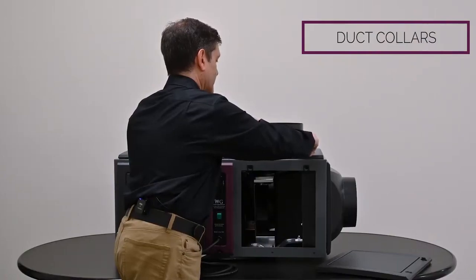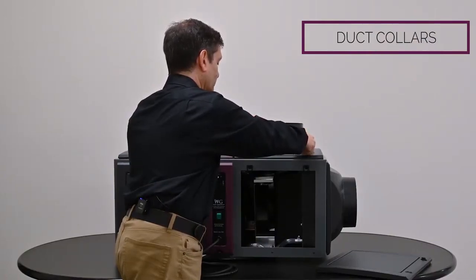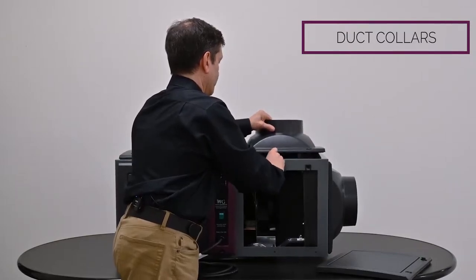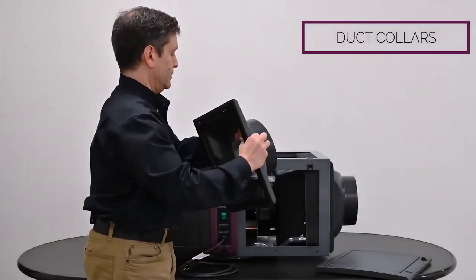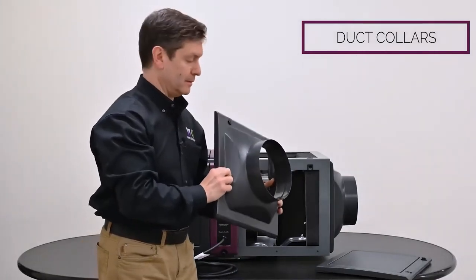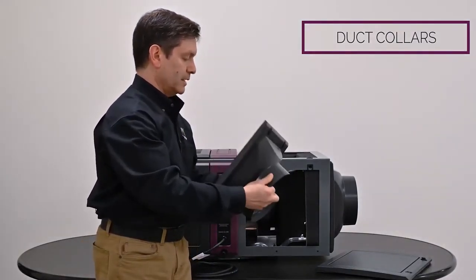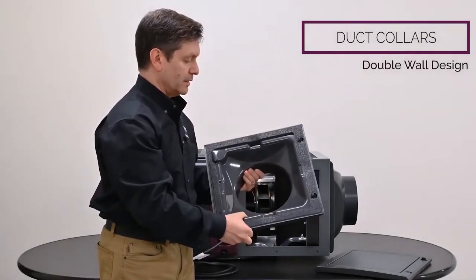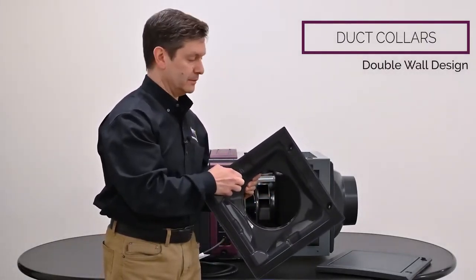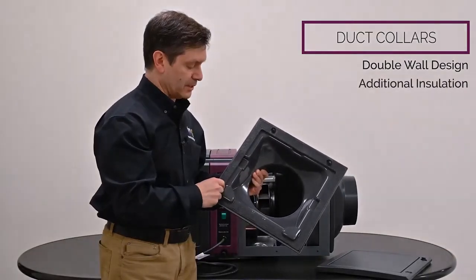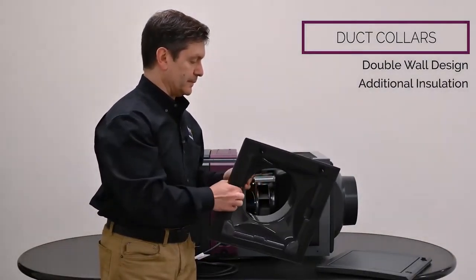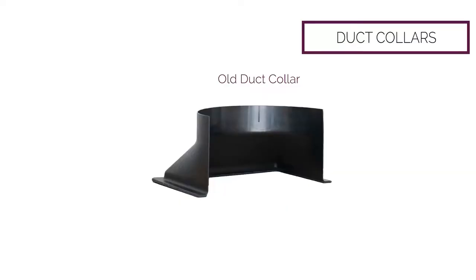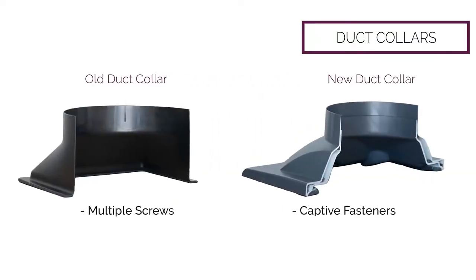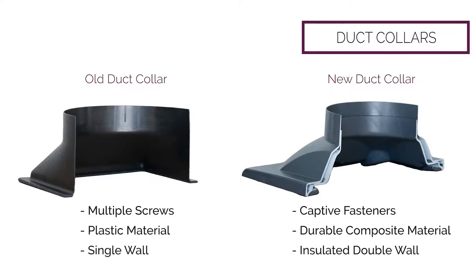And again, this fastens the same way as our removable solid panels. Very easy. No number of screws to take off. But this is a double-walled, heavy-duty duct collar connection. You'll notice that we've got insulation as an extra barrier, far superior than the old design, if you're familiar with that, both in the way it fastens to the unit, its construction, its durability, and it will not sweat. It's double-wall insulated, it will not sweat.